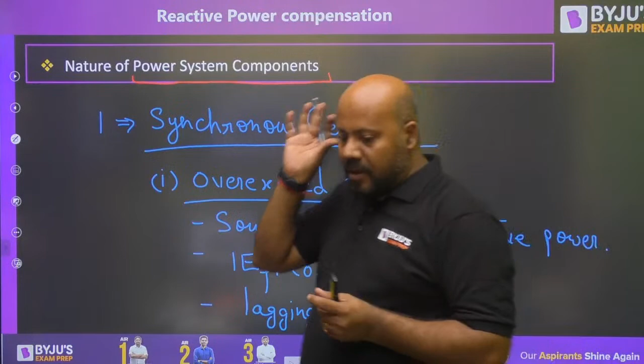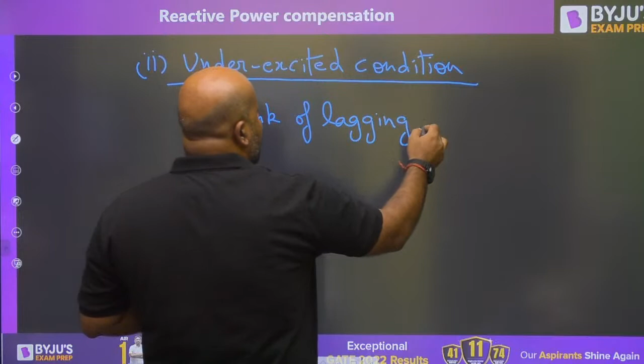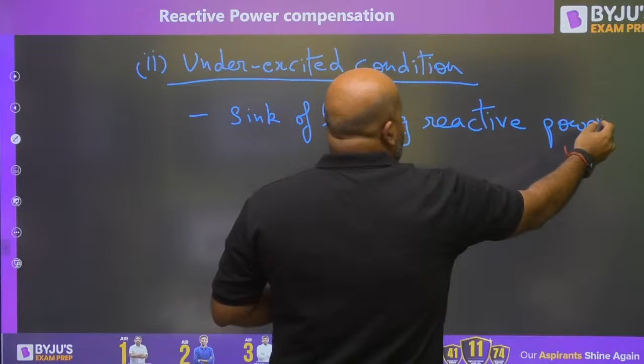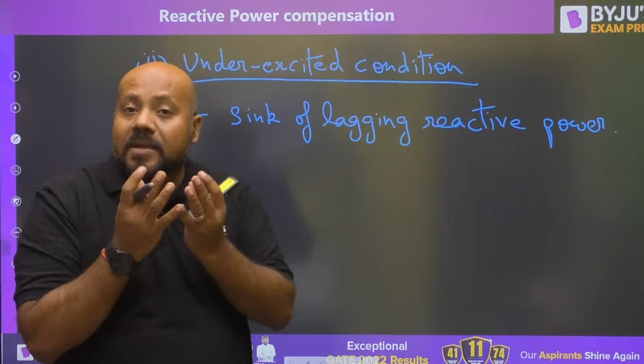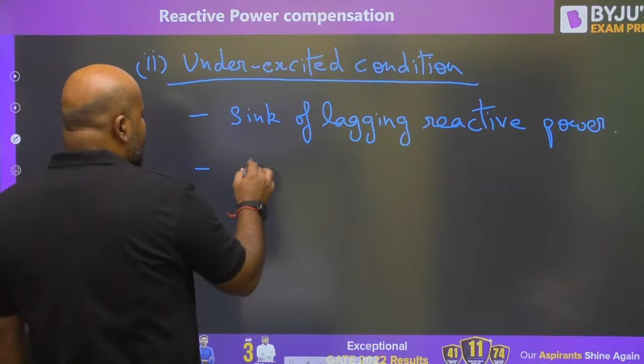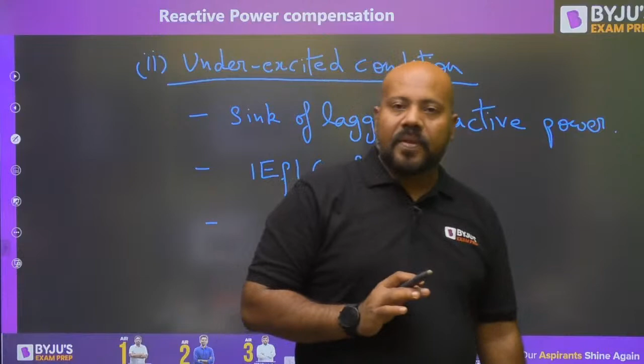The second condition is the underexcited condition. In the underexcited condition, your generator is going to act as a sink of lagging reactive power. What is the meaning of sink of lagging reactive power? It means that in the underexcited condition, your generator is going to absorb, that is, act as a load for, lagging reactive power. The condition is mod EF cos del is less than mod V. And what is the operating power factor? Now you can judge, now you can guess it.